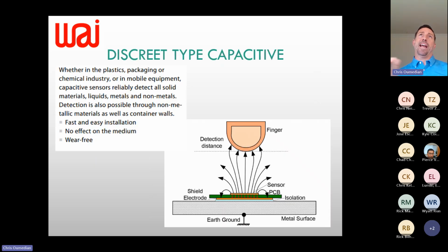So those all offered analog. Some folks just need a discrete signal, and we're going to wrap up with two types of discrete signals. This would be a capacitive sensor, and these would be mounted on a sight glass or the outside of a plastic or poly tank. And as the media passes that sensor, goes up and down, that sensor is going to output. Capacitive sensors are based on differential and dielectric constant, which is a property in all materials. We've got lookup tables, and it will switch.